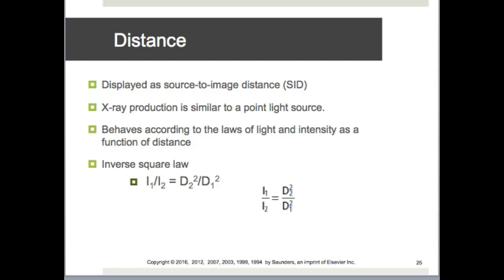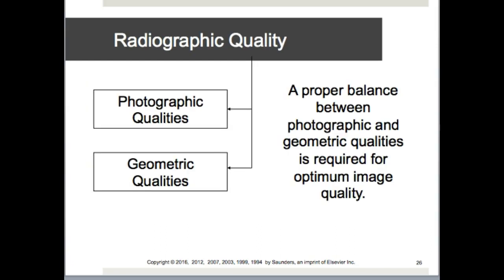So as we change our distance, it'll tell you the difference in the intensity of the light with the change in distance, or the density of photons. So light and photons behave the same. So with the divergent beam, if you go from 40 inches to 72 inches, you are able to calculate the intensity so that you can pick the proper technique.